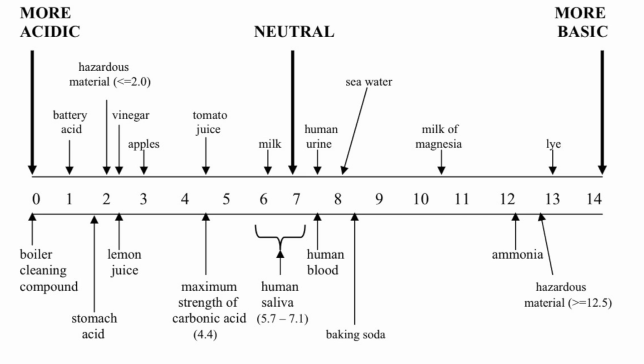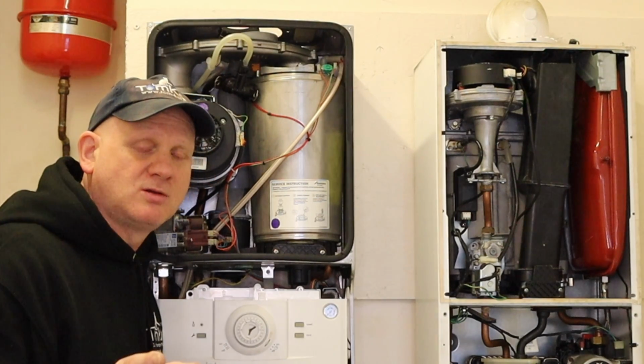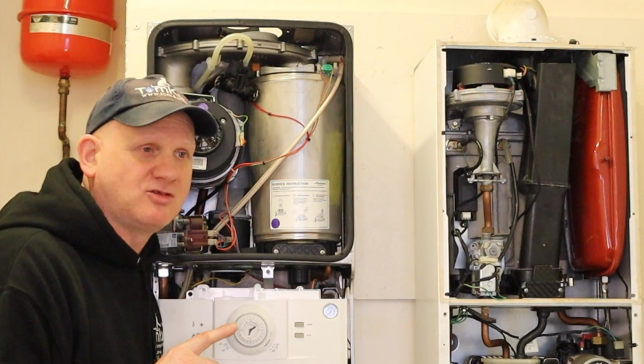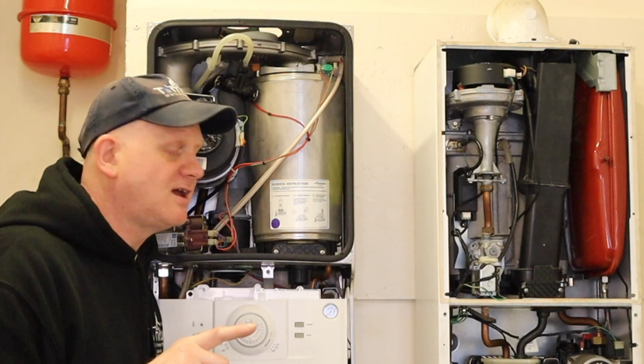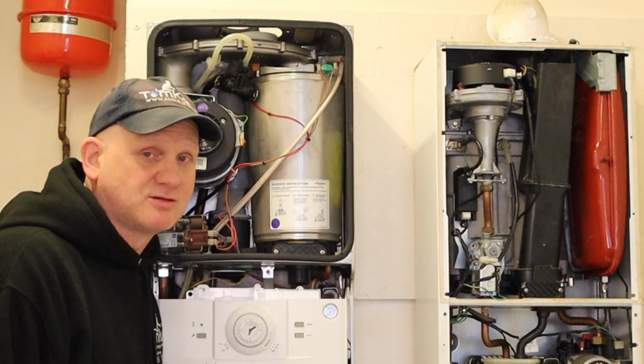Now the aluminium heat exchangers must be kept between 6.5 and 8.5 on the scale, but stainless steel heat exchangers have a far bigger range on the pH scale than aluminium and copper. For this reason alone, stainless steel heat exchangers are far more robust than the aluminium or copper heat exchangers. So, that's aluminium heat exchangers. Let's now have a look at stainless steel ones.